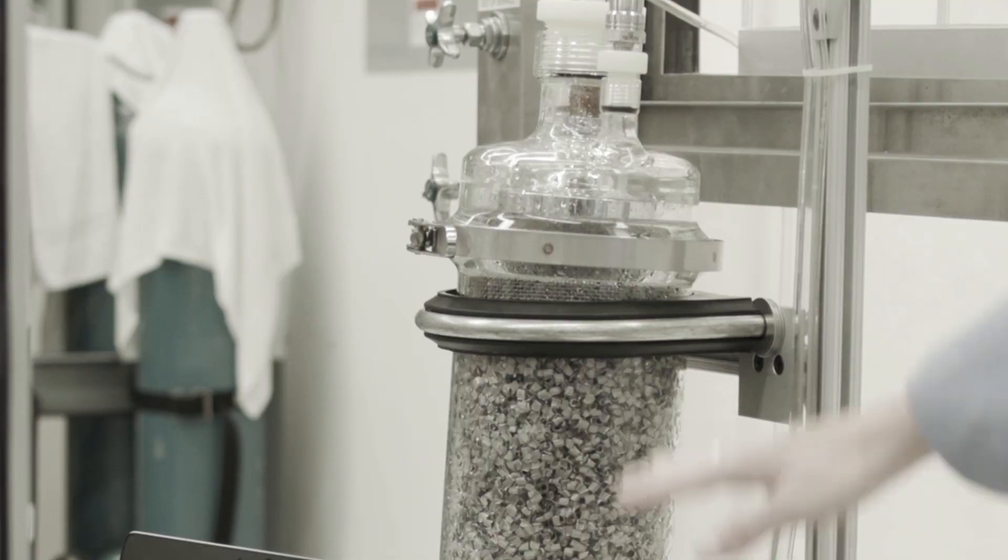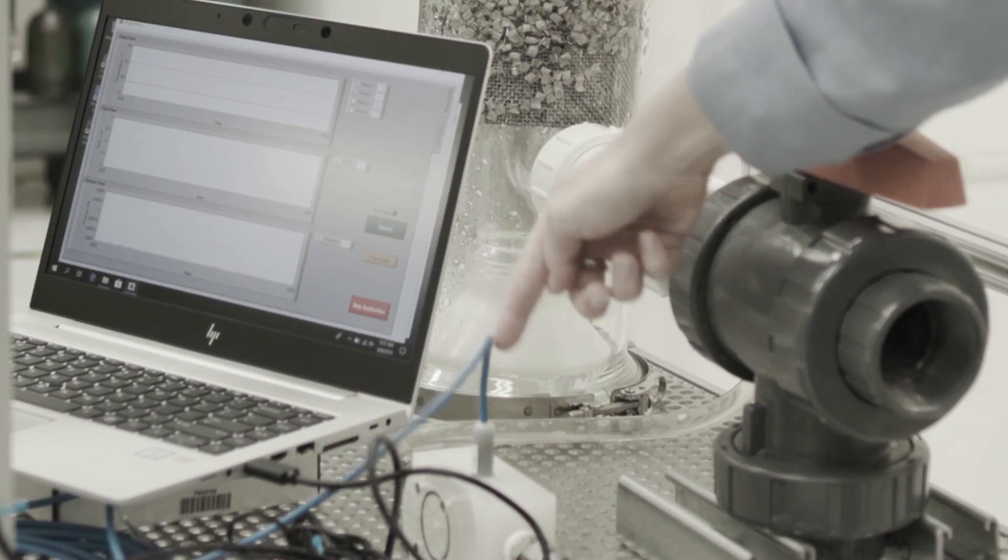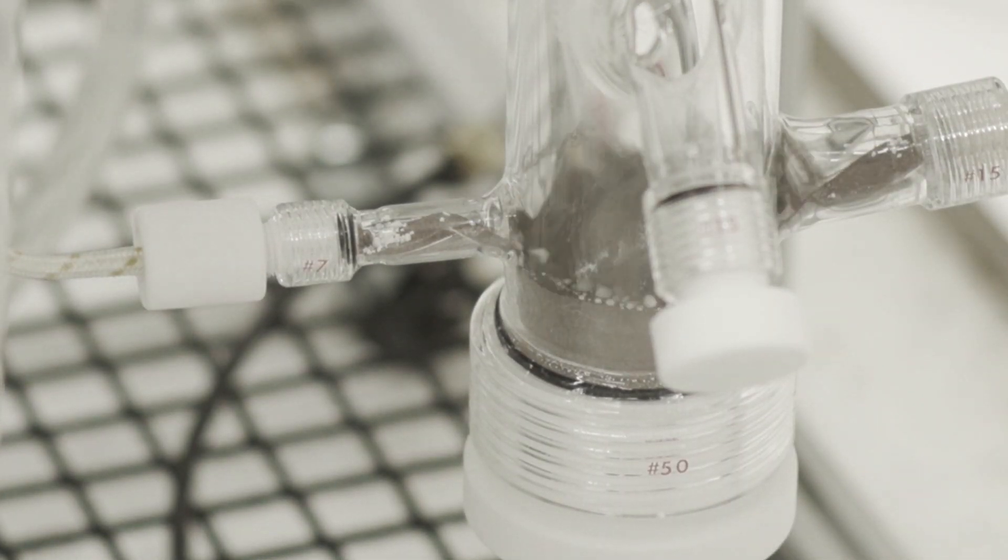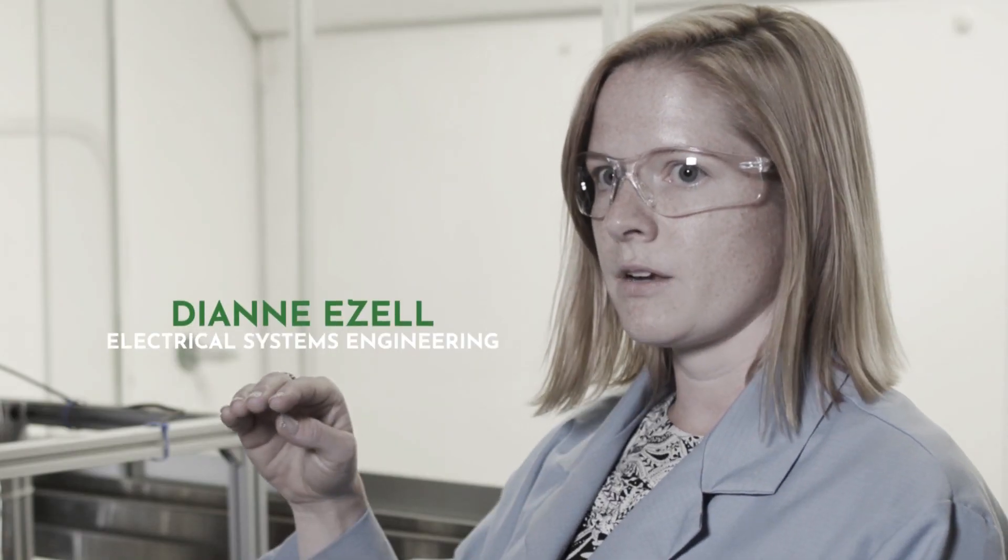On this system we monitor the pressure, the flow, and the temperature. In the aerosol generator we're using a 1.5 micron particulate and you want to see that it's separating from your liquid the way we've designed it to.